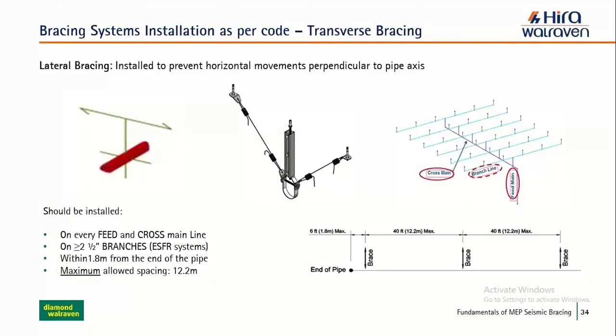Then the lateral sway brace has its own standards to consider for the span, and the longitudinal sway brace has its own standards for the span. As you can see here, it could be applied on every feed and cross main line for the piping, and it is used mostly for pipes greater than 65 mm in diameter. It should start 1.8 meter from the end of the pipe, and the maximum allowed spacing is 12.2 meter for transverse bracing, lateral bracing.